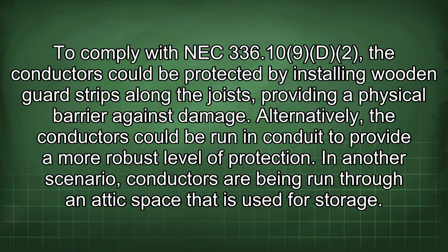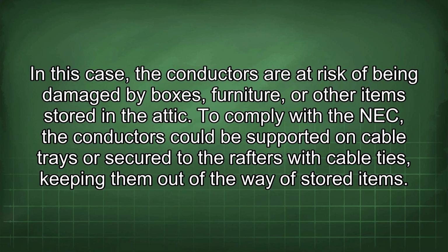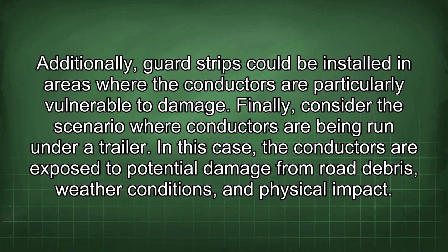In another scenario, conductors are being run through an attic space that is used for storage. In this case, the conductors are at risk of being damaged by boxes, furniture, or other items stored in the attic. To comply with the NEC, the conductors could be supported on cable trays or secured to the rafters with cable ties, keeping them out of the way of stored items. Additionally, guard strips could be installed in the areas where the conductors are particularly vulnerable to damage.